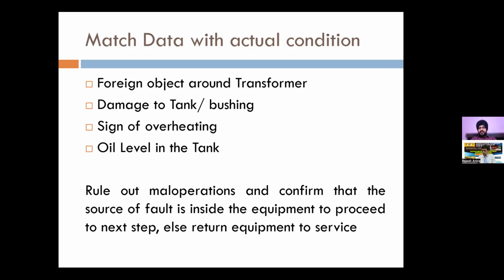So you need to rule out these foreign objects, and then you also need to identify whether there is any significant damage to the tank or the bushing. Even if you have identified that this is a maloperation, you still need to check whether there has been any other damage to our tank or bushing. You need to see if there is any overheating. It is advisable to do a thermovision scanning of the transformer just to see whether any hotspot is getting formed. Check the oil level in the tank, and if the PRD has operated, whether oil has actually been released or not. So these factors you need to verify so that you can gather some more data.